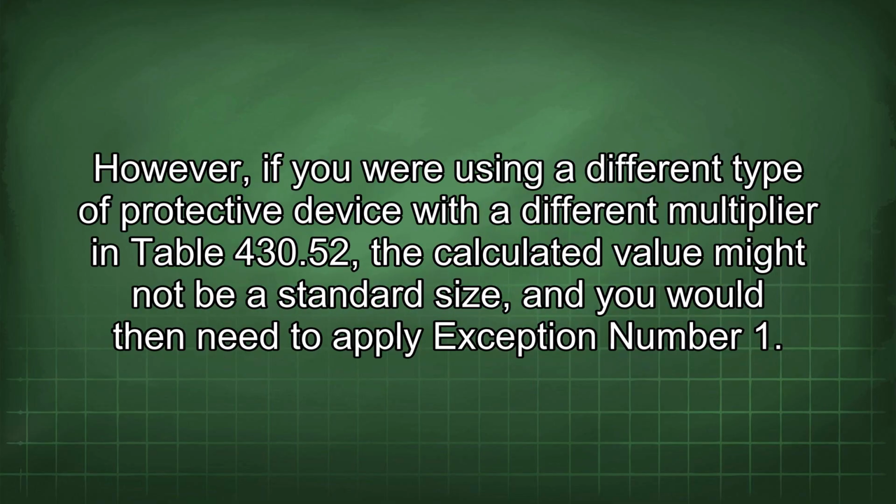However, if you were using a different type of protective device with a different multiplier in Table 430.52, the calculated value might not be a standard size, and you would then need to apply exception number 1.